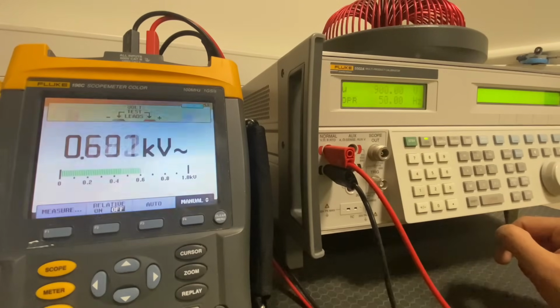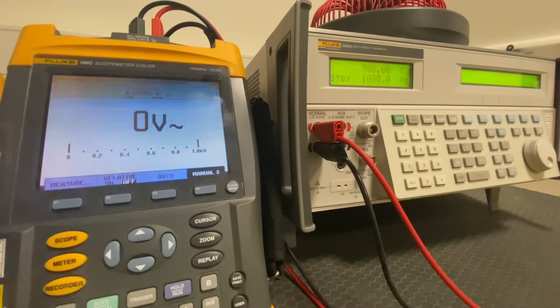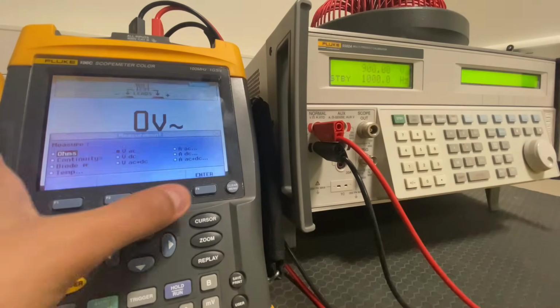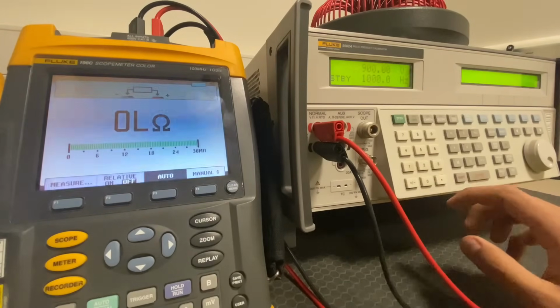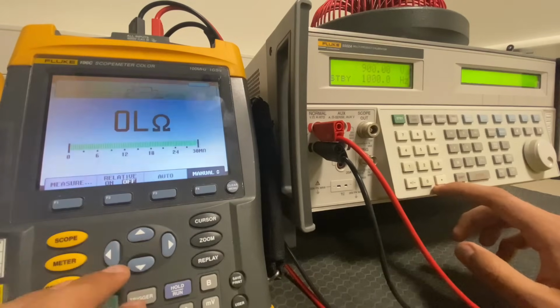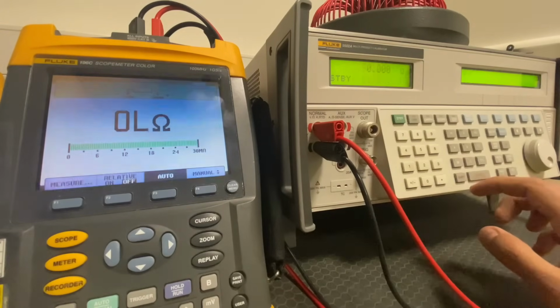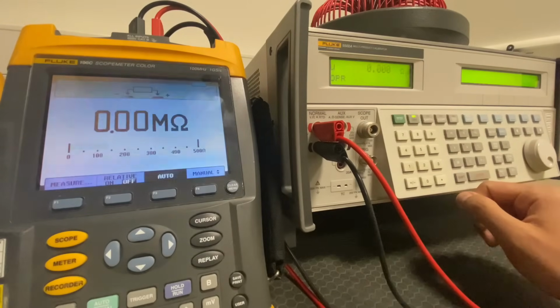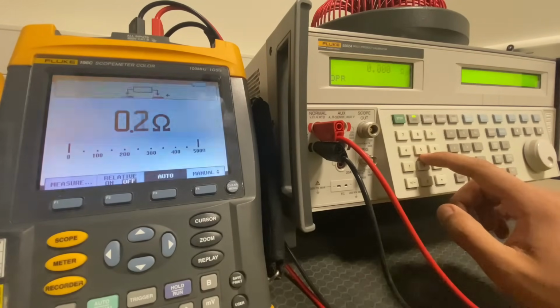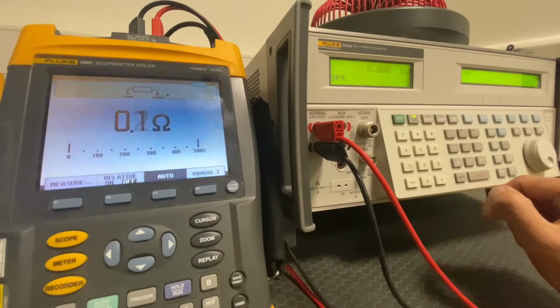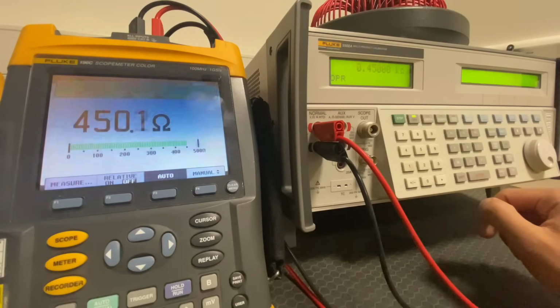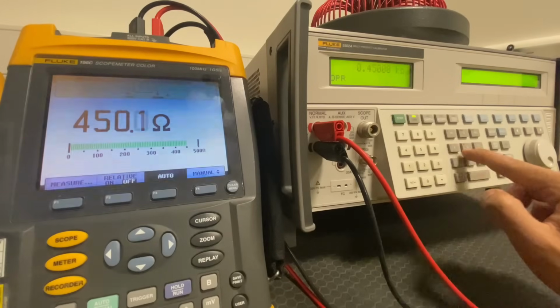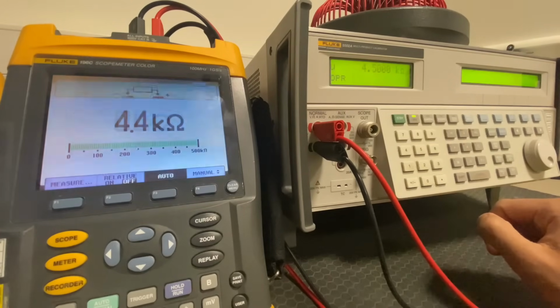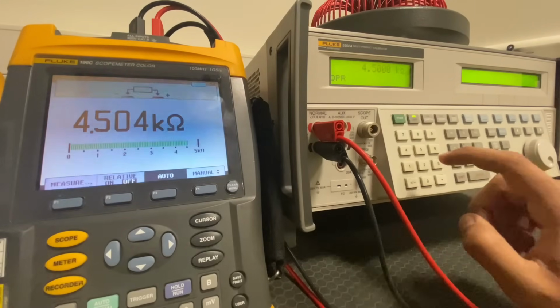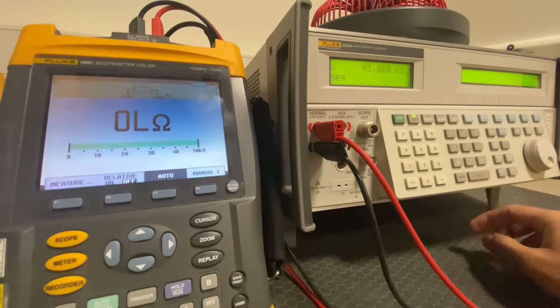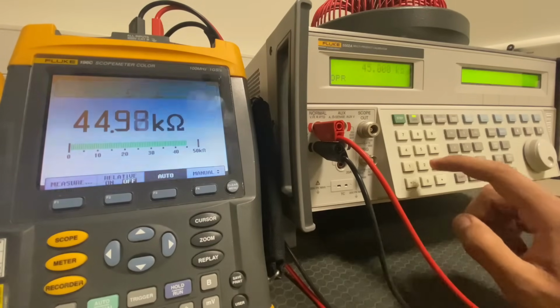Now we can move on to resistance measurements. As the first step, 0 ohms. Let's check. Now we will measure 450 ohms. The ranges here are as follows: 5 kilo ohms, 50 kilo ohms, 500 kilo ohms, 5 mega ohms, and 30 mega ohms. Here we are taking measurements close to the highest values of the range.